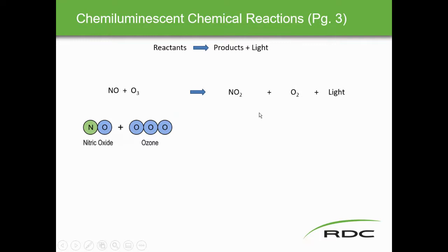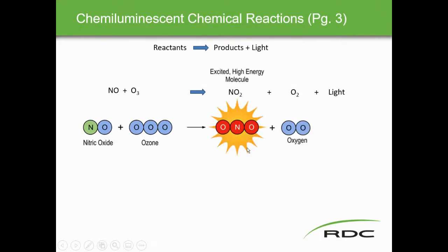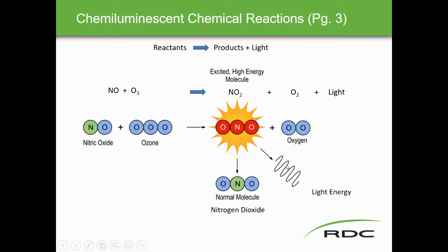In this reaction, we have NO (nitric oxide) and O3 (ozone), and once they react we produce NO2 (nitrogen dioxide), plus oxygen, plus light energy. The amount of light energy is proportional to the amount of nitrogen dioxide in the sample. This is the whole reaction that the analyzer is looking for.